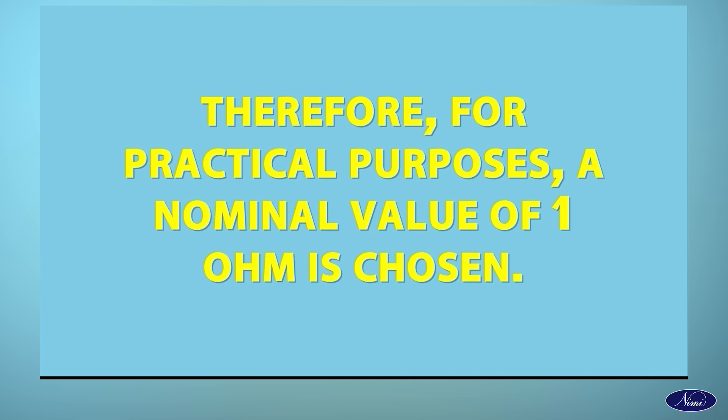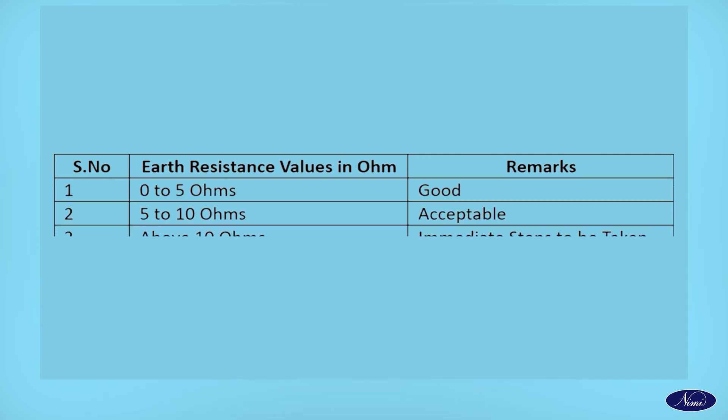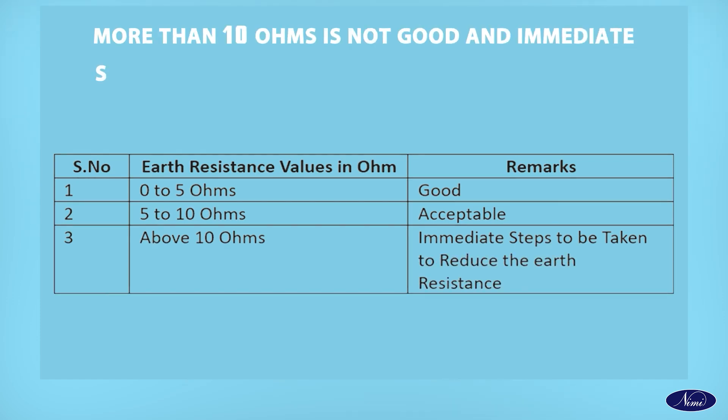Therefore, for practical purposes, a nominal value of 1 Ohm is chosen. Earth Resistance should be maintained between 0 and 5 Ohms and up to 10 Ohms can be acceptable. More than 10 Ohms is not good and immediate steps should be taken to reduce it to normal values.